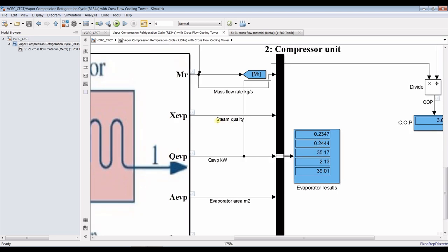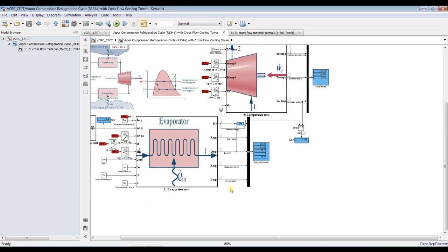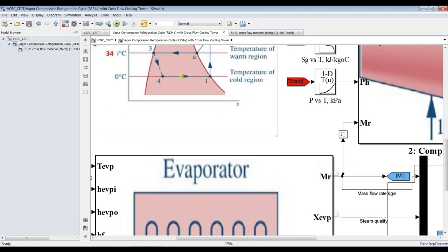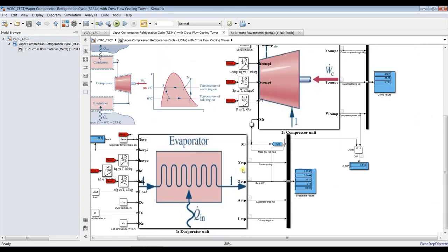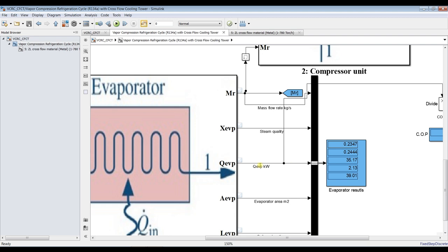This is steam quality, 0.2444. Okay, steam quality, as you can see on the TS diagram. This is your steam quality and the thermal load on the evaporator. Okay, it's around 35 kilowatts. Okay, this is 1, 2, 3. So this is value 1, 2, 3, okay.